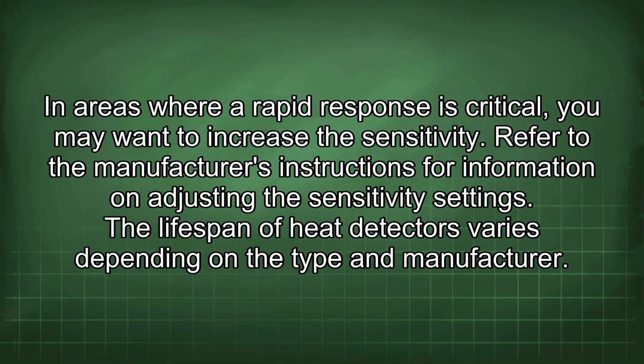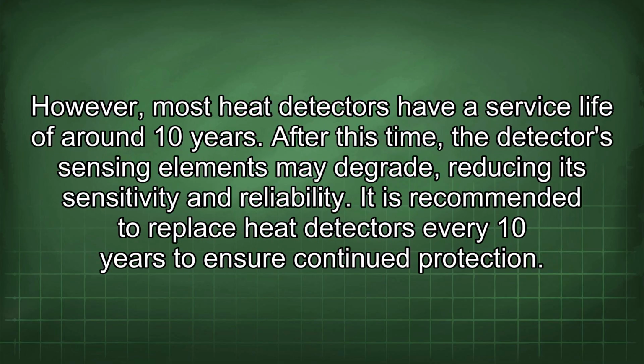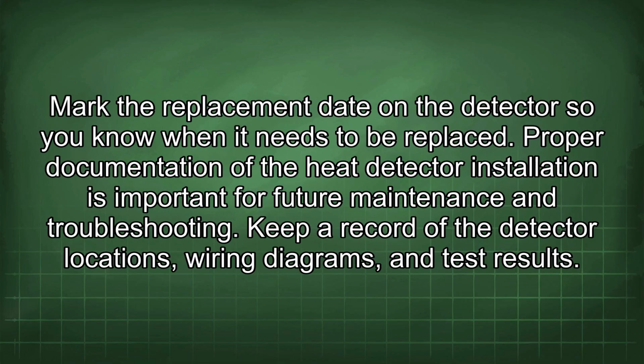The lifespan of heat detectors varies depending on the type and manufacturer. However, most heat detectors have a service life of around 10 years. After this time, the detector's sensing elements may degrade, reducing its sensitivity and reliability. It is recommended to replace heat detectors every 10 years to ensure continued protection. Mark the replacement date on the detector so you know when it needs to be replaced.